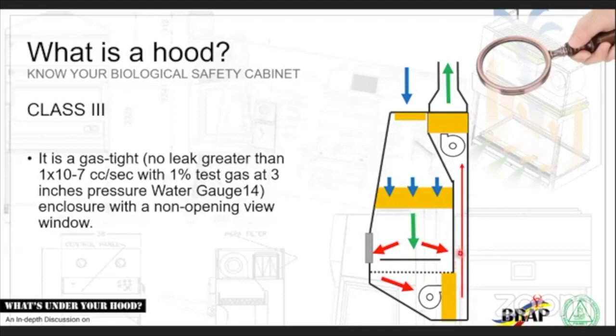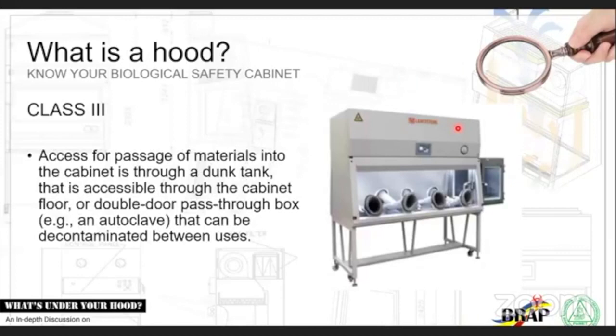So you have your negative pressure in this area. You have a negative pressure in this area caused by this one. And this front grill or sash is sealed. You cannot open that. You have your gloves there. And this one is hard ducted outside. So you have several layers of protection. 1, 2, 3, 4 filters before everything gets exhausted. This is an example of your Class 3 biosafety cabinet. There's a very old version wherein there's a very big Class 3, and you have to go under the Class 3 biosafety cabinet and actually insert yourself here wearing, let's say, a half coverall, or sorry, half positive pressure suit. So that's how it worked before.